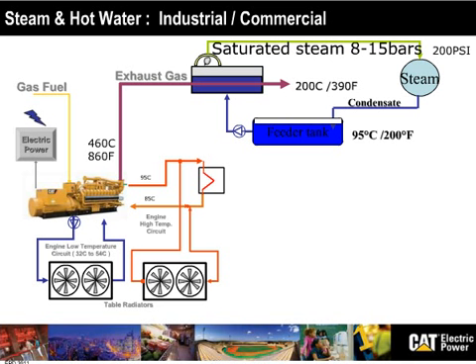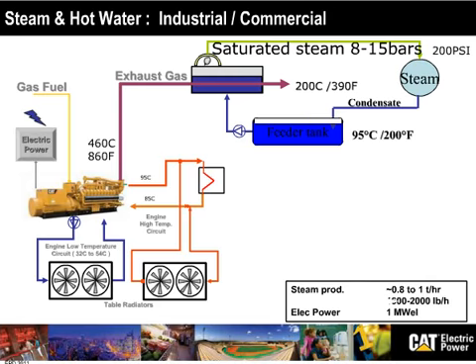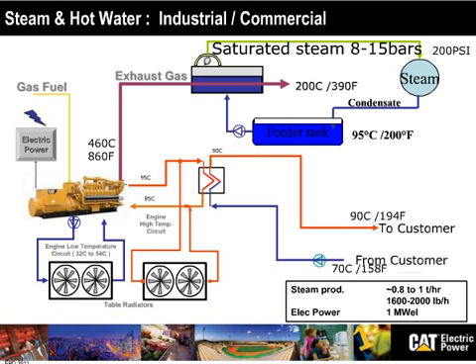Then you can produce 8 to 15 bars, and this is enough to produce 1 ton of steam per electrical megawatt. And this is modest, but we can only use the exhaust gas to produce saturated steam at that pressure. All right. Now, if at the same time you also want hot water, in combination you can produce hot water and steam together using the exhaust gas for steam and the jacket water for hot water. So 1 ton per hour for 1 megawatt. In some applications, this might not be required.